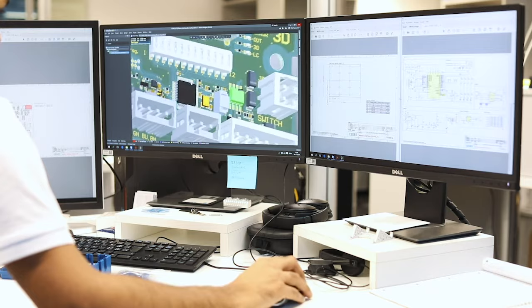The Capsafe controller is currently available with 24V DC input power with either a solid state output or a potential-free relay output. Users can also choose whether they want the controller as a bare printed circuit board, a printed circuit board on a DIN rail-mounted PCB carrier, the printed circuit board in an enclosure, or a wide-ranging Capsafe MOD controller that supports both 20 to 37V DC and 120 to 240V AC, which is currently under development. Status indicators on the Capsafe controller show the status of the Capsafe 2D and Capsafe 3D devices, as well as any error condition that could exist.